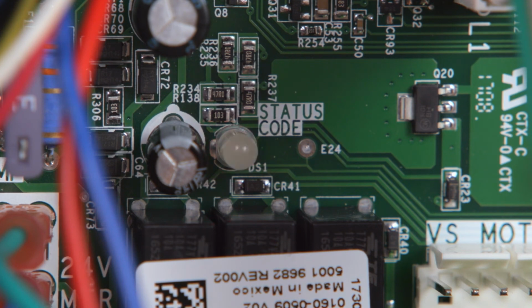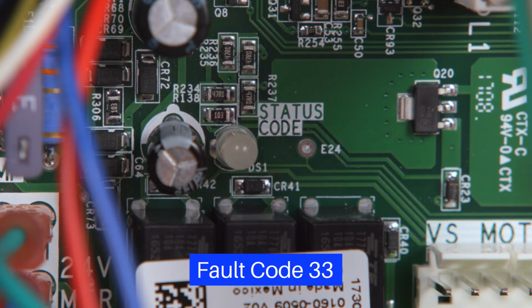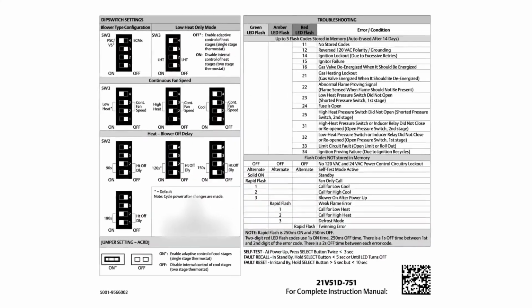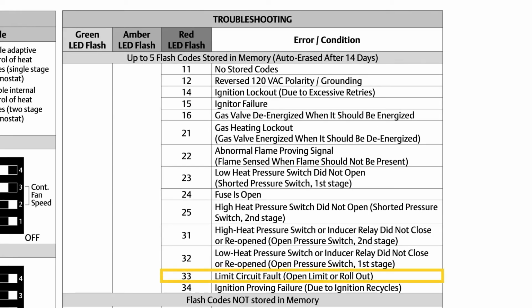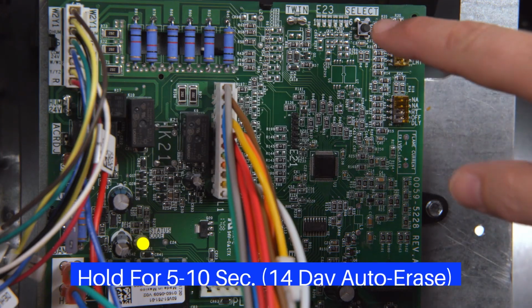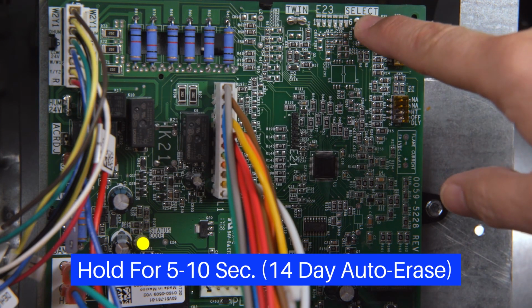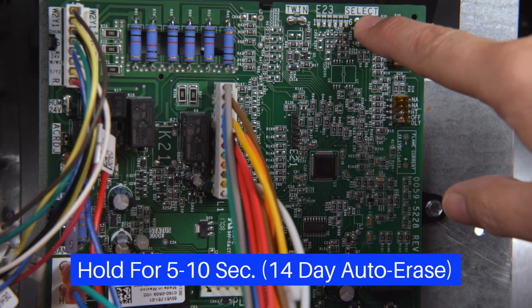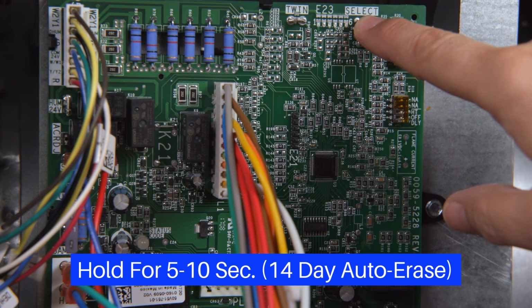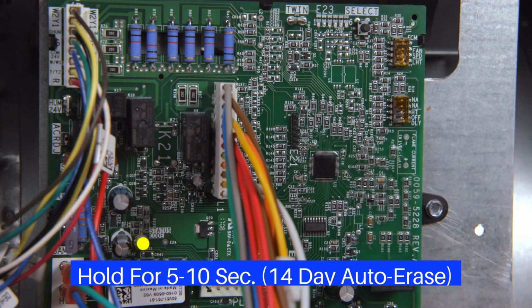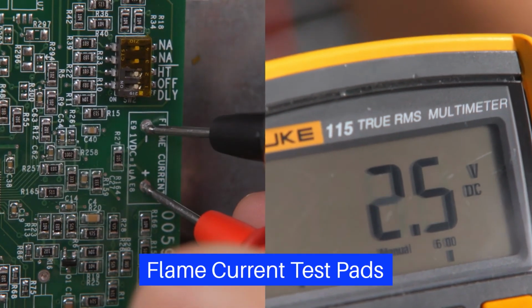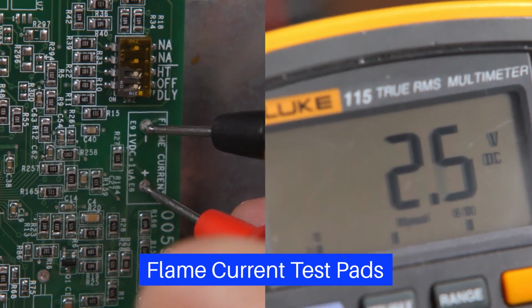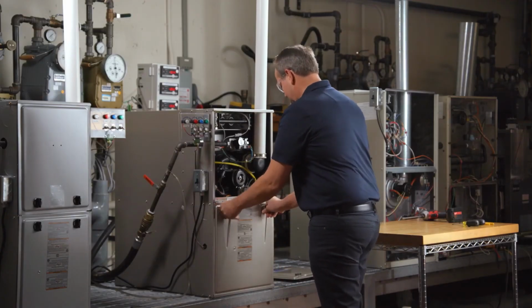If any faults occur during the cycle, a flash code will indicate the fault. The LED is displaying 3 short followed by 3 long red flashes. The fault is repeated after a 2-second delay. A control label indicates a limit circuit fault. To clear the fault codes, press the fault code button labeled Select for 5 to 10 seconds. The flame current test pads are easy to access and provide the flame current reading. Reinstall any panels that were removed.